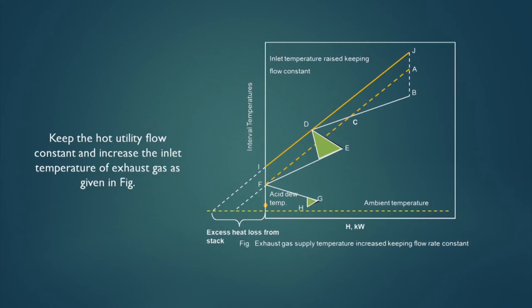The third method is to keep the hot utility flow constant and increase the inlet temperature of the exhaust gas — shifting the entry point of the exhaust gas from A to J. By doing so, the hot utility line is now able to service all parts of the GCC, whereas at the original position it was not able to serve the D-to-C part of the GCC curve. We have to examine whether we can increase the exhaust temperature of the GT by that much, as it will affect the GT performance.